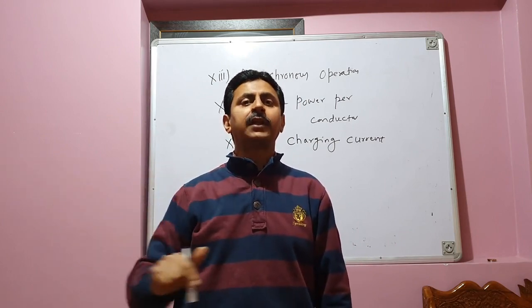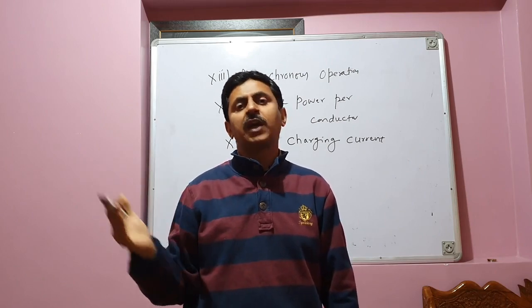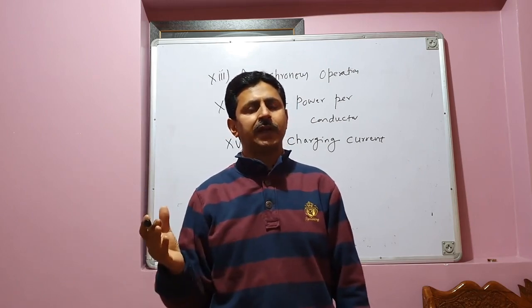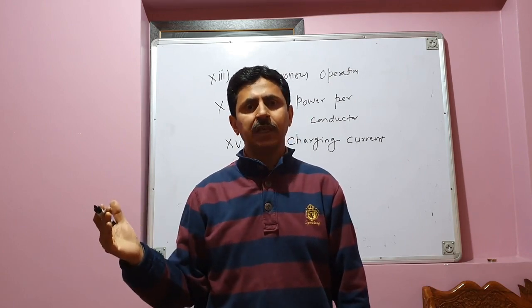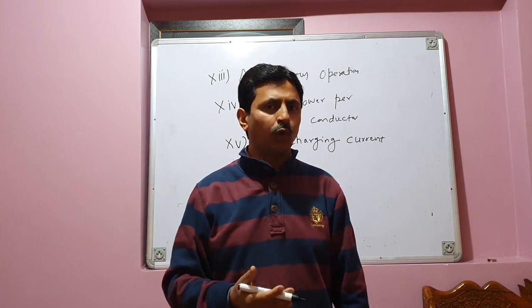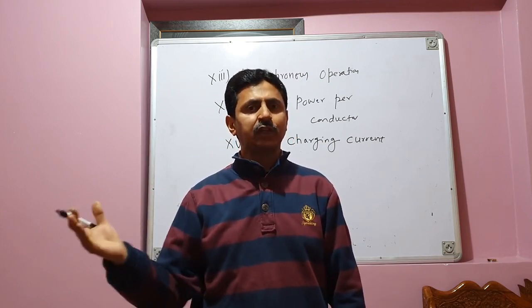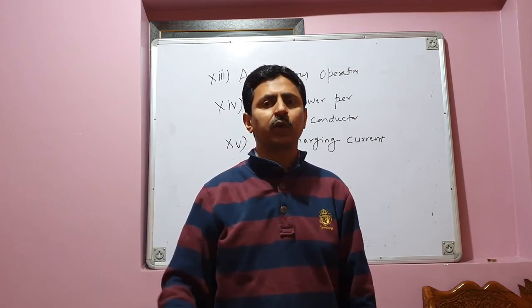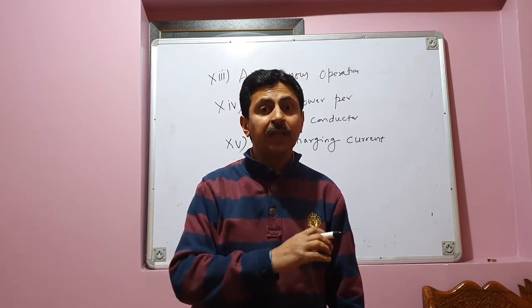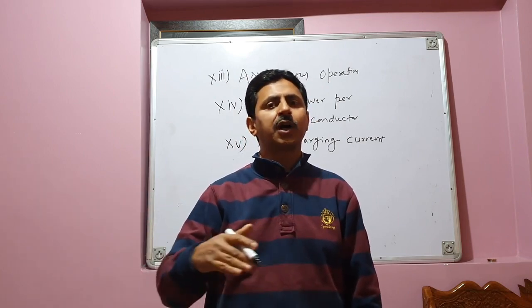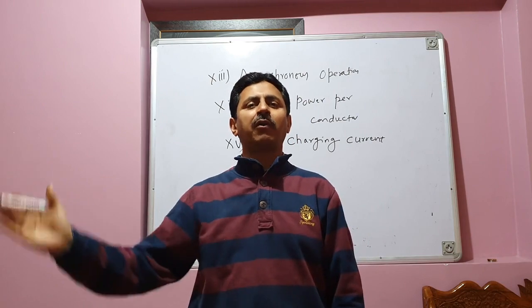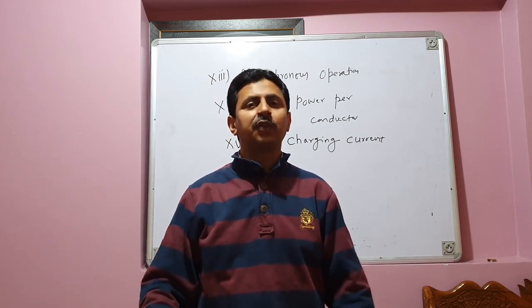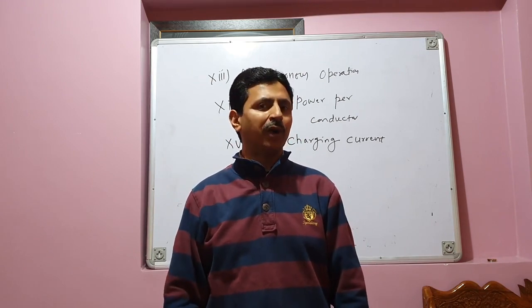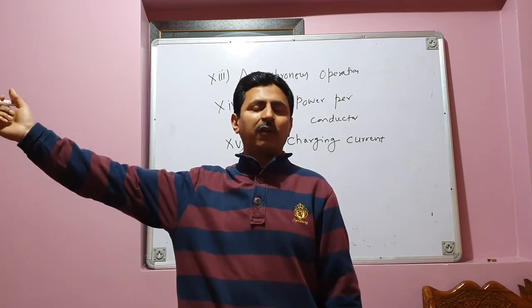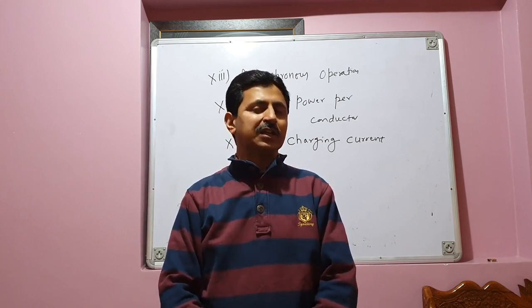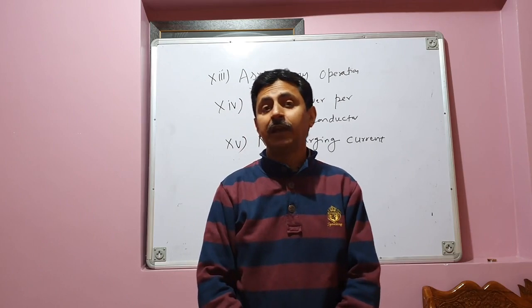Charging current is basically the capacitive current, and it is at 90 degrees with respect to the voltage. And any current which is in quadrature with the voltage, it means what power? It means reactive power. So whenever a large charging current is flowing in the underground cables, that means only reactive power is flowing. And the magnitude of charging current may be so high that only reactive power may flow through the underground cables, and it will leave no room for the flow of active power. So you will not be able to make any active power flow through underground high voltage AC cables. That's why we never go for underground power transmission.